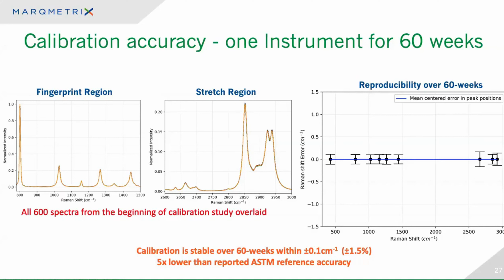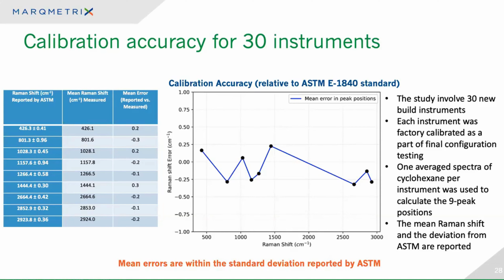Speaking of that, I'd like to look at not just an instrument, but let's look at the last 30 instruments we built and look at the calibration accuracy when they were built. Here we see about the same exact distribution across 30 individual systems that were built. Looking at the same ASTM standards, it's better seen graphically, and we look at the distribution plot. We see about negative 0.25 to positive 0.25 wave numbers in the distribution of our last 30 instruments manufactured. This calibration stability, along with the reproducibility between instruments that we can manufacture, allows us to actually apply global models to reduce the cost of ownership and implementation for Raman.